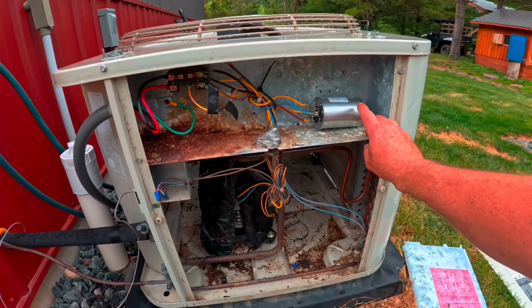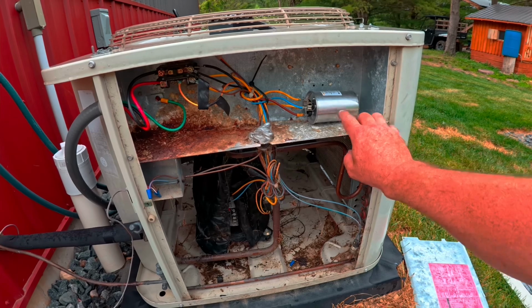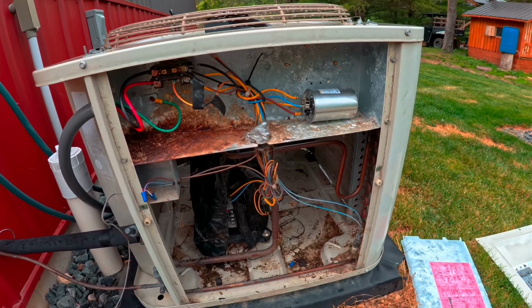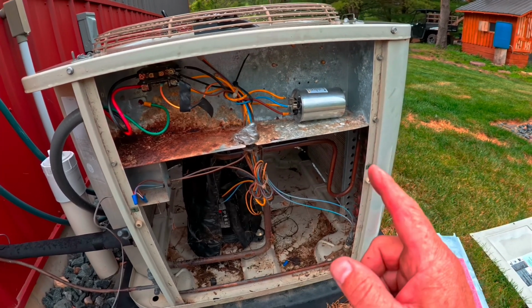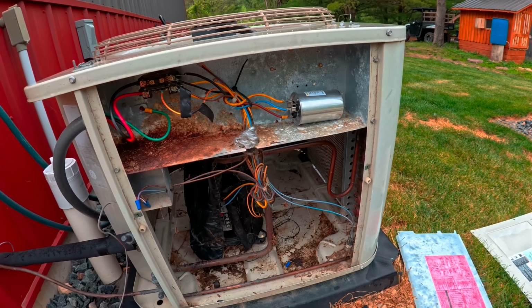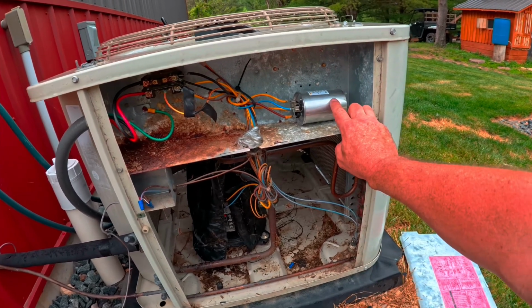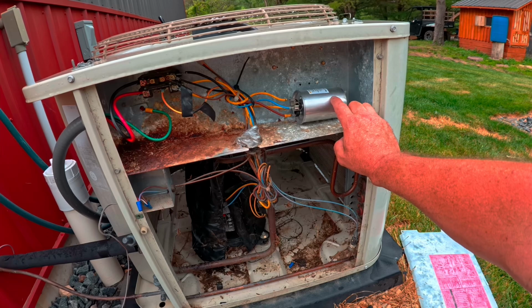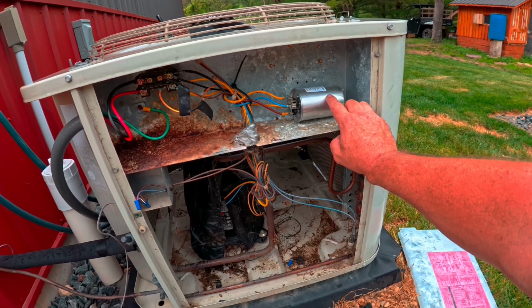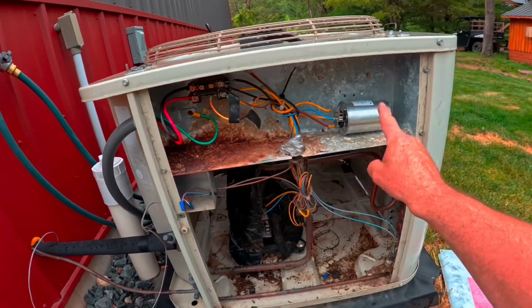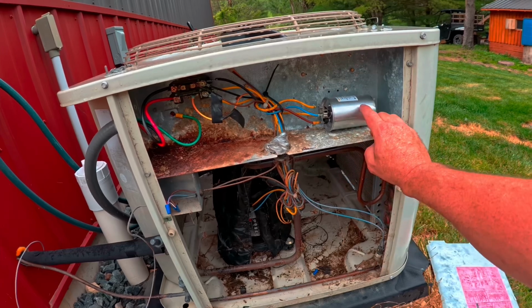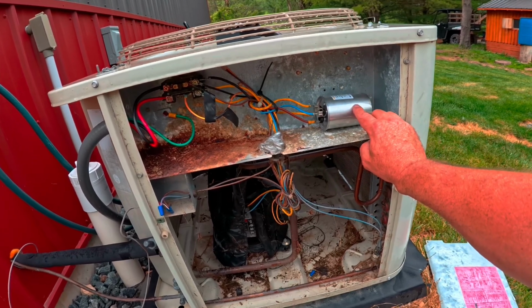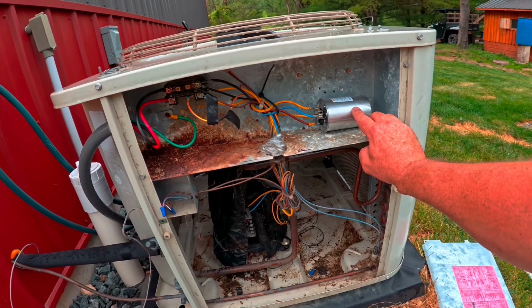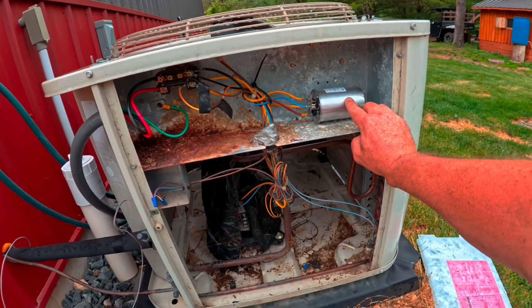To replace this is easy, and if you see any signs of it leaking oil and stuff like that, it needs to be replaced. This one here was replaced, according to my notes that are written on here, in 2017, and I do think I replaced this again since then. They do fail. The contactors fail, these fail. They're wear items. Anyways, this can be replaced easy enough by following the rules, okay?